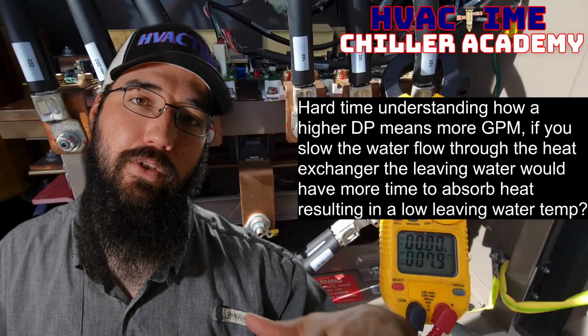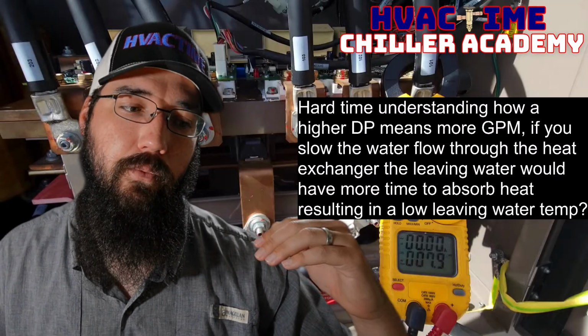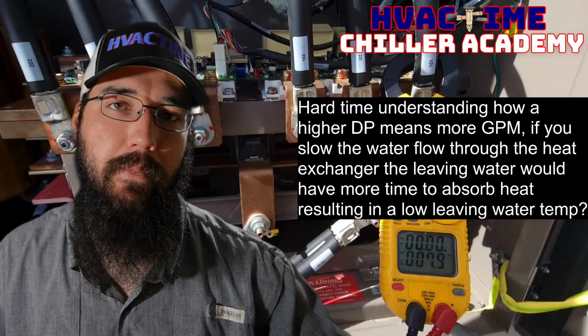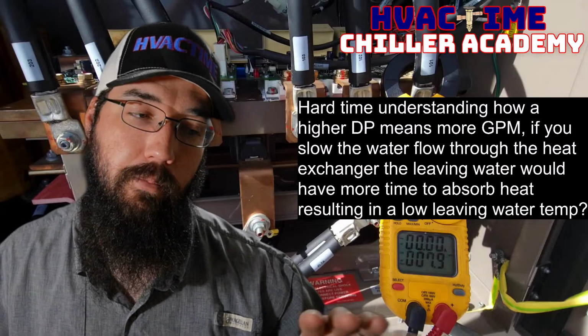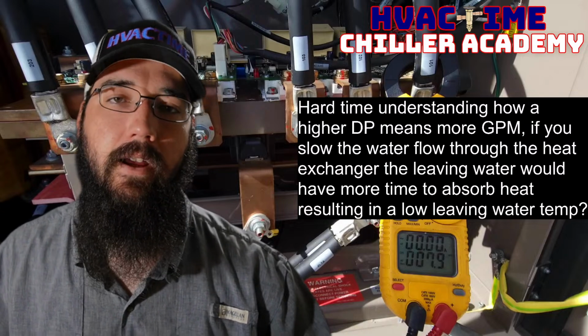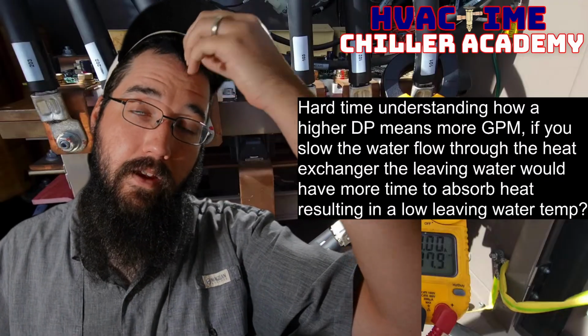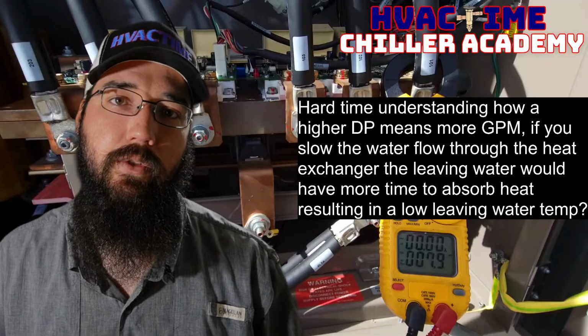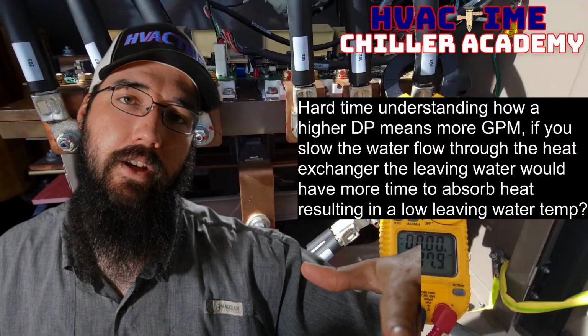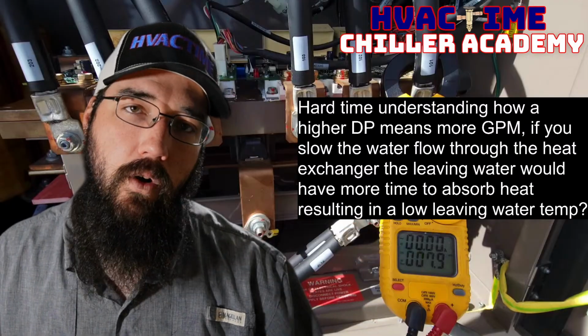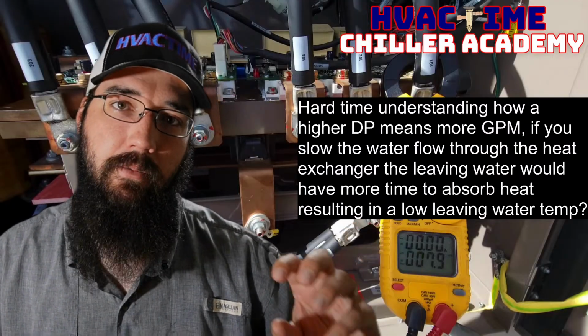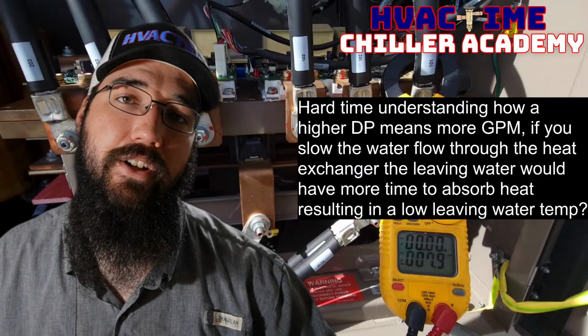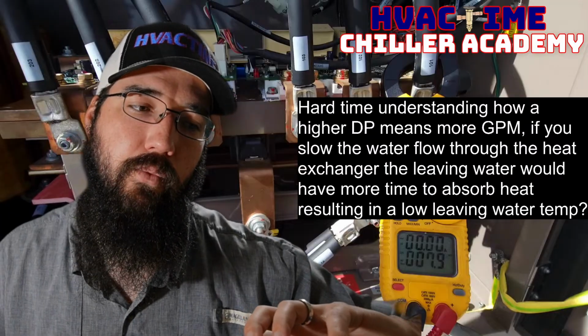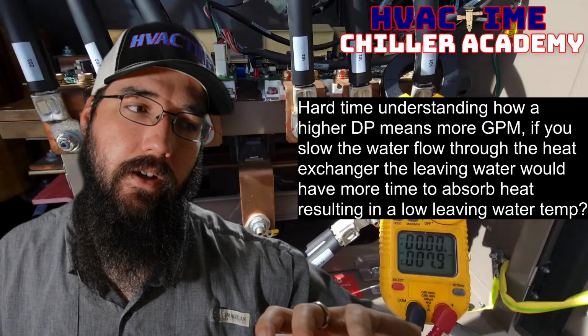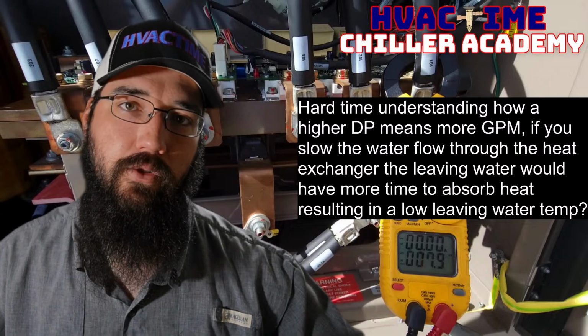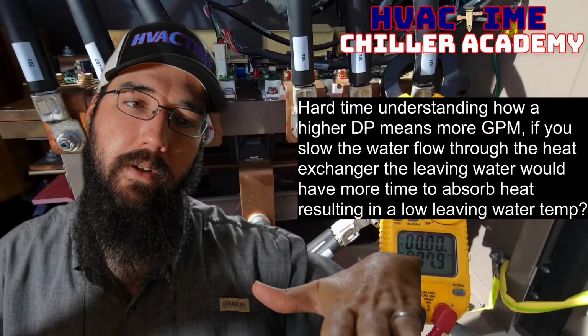So we can force so much flow through the heat exchanger that we're ramping that compressor as much as we can't make set point properly, or we're pushing the compressor way past where we should to get there. I've had that where you start having these crazy approach values, because we're trying to overstage the compressor in order to get the water temperature down, because we have so little contact time.